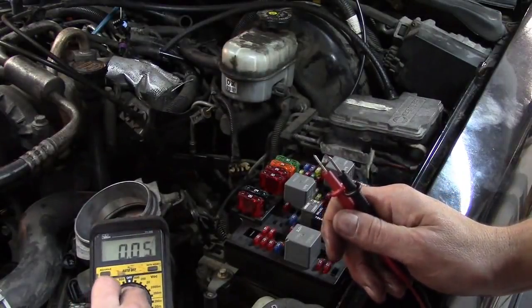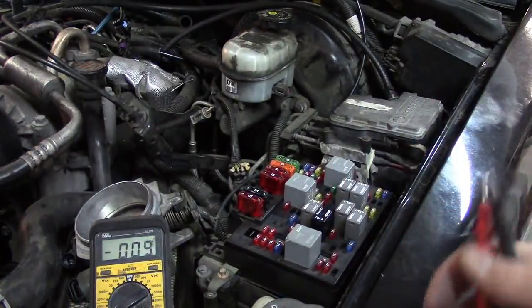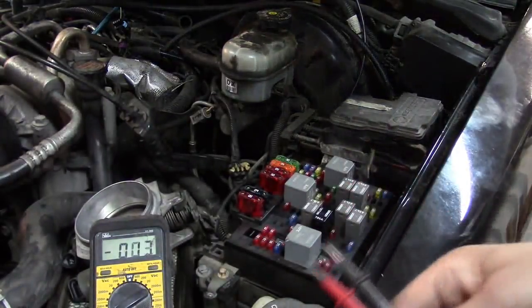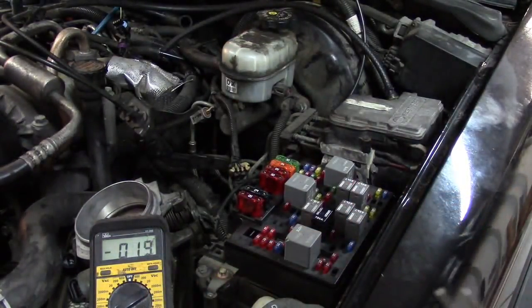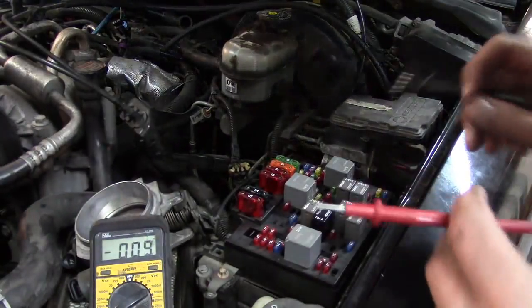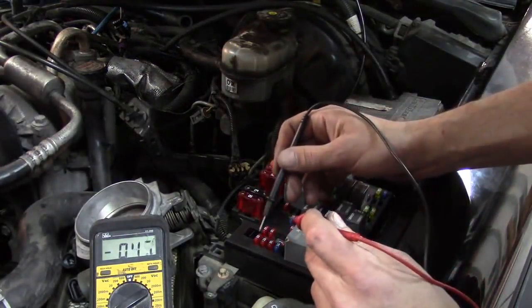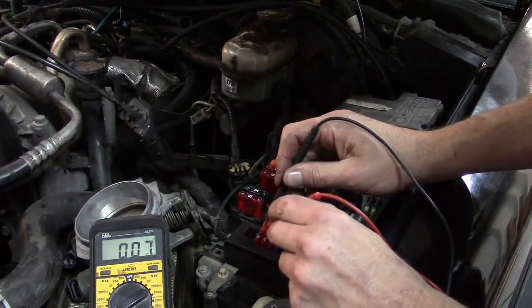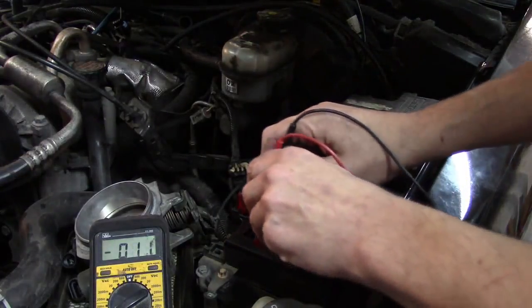We're going to have a very minimal amount of voltage drop, so we need to set the meter to a millivolt scale. If you do not have millivolt detection with your DVOM, this test probably won't work. All we have to do is test the contact points on the fuse and see if we have any voltage drop.